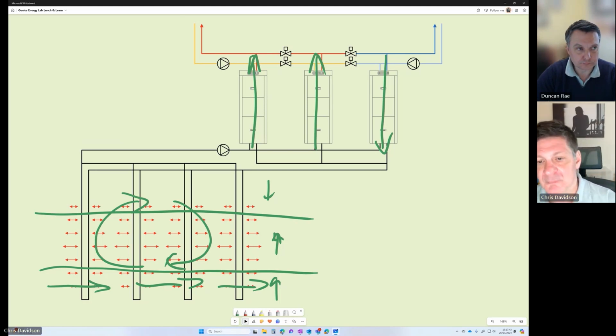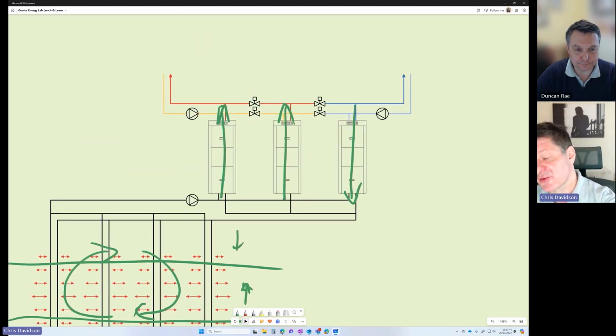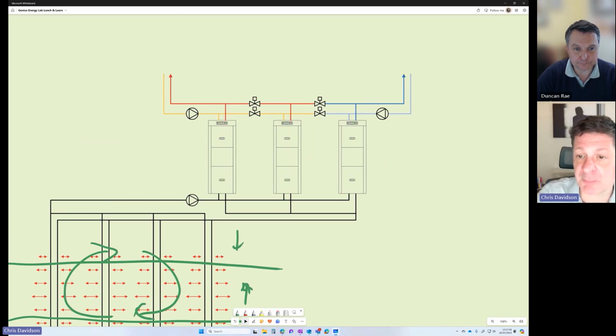Let's now look up into the building. This is what we call a sliding header. So what we've got here is we've got one heat pump cooling, as I said, two heat pumps heating. So these valves here would be shut, these valves will be open. And let's say we're now moving into the summer, as we hopefully are at some point.